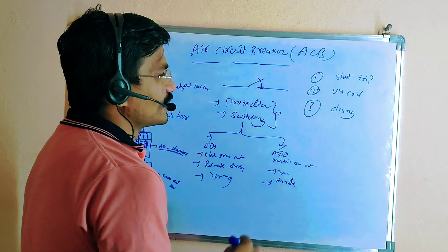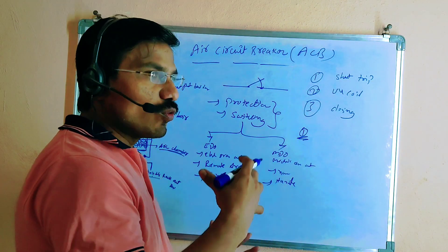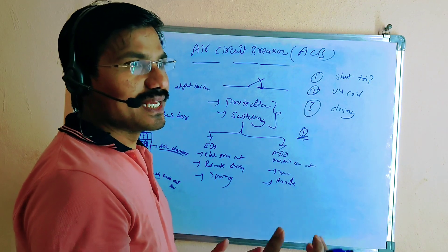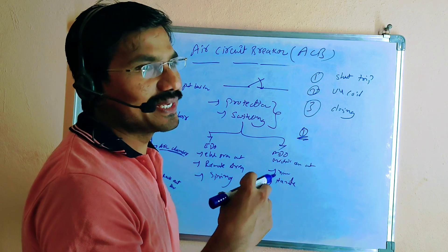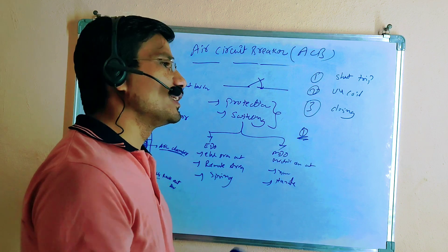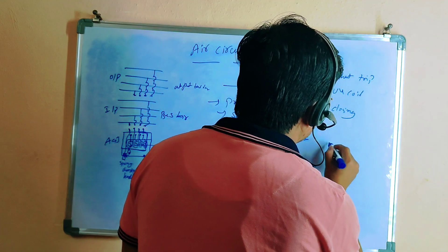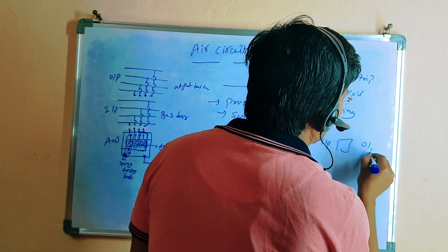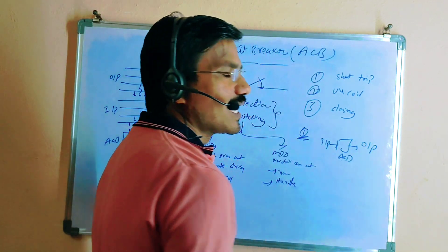In this breaker there are three main parts: the shunt trip coil, the UV coil, and the closing coil. The shunt trip coil means that if any fault occurs at the output, the relay automatically gives a trip command, and the breaker trips — isolating the input from the output.